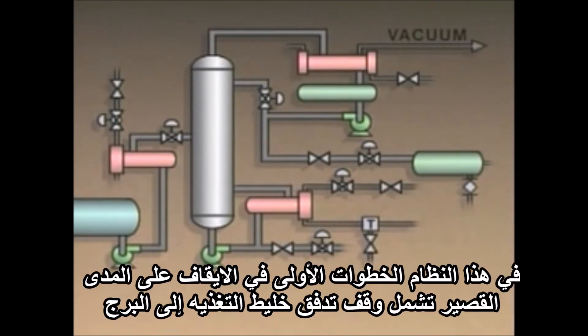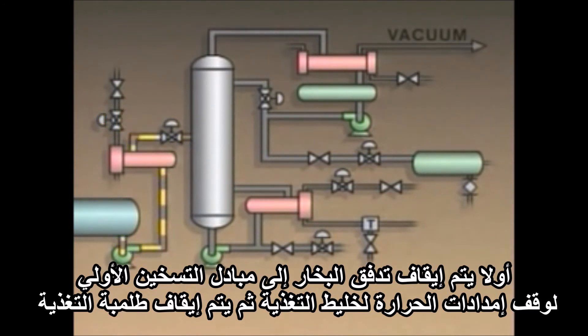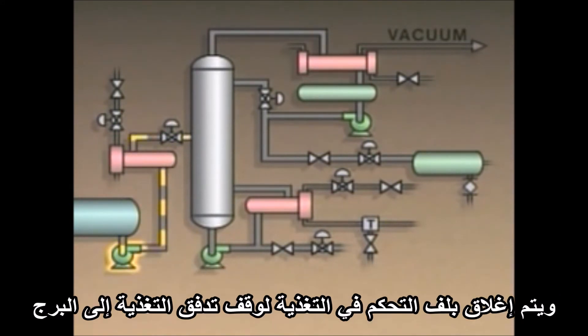In this system, the first steps in the short-term shutdown involve stopping the flow of feed mixture to the column. First, the steam flow to the preheater is shut off to stop the supply of heat for the feed mixture. Then, the feed pump is shut off and the feed control valve is closed to stop the flow of feed to the column.